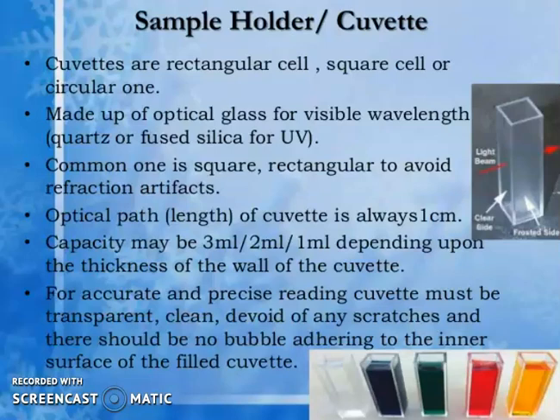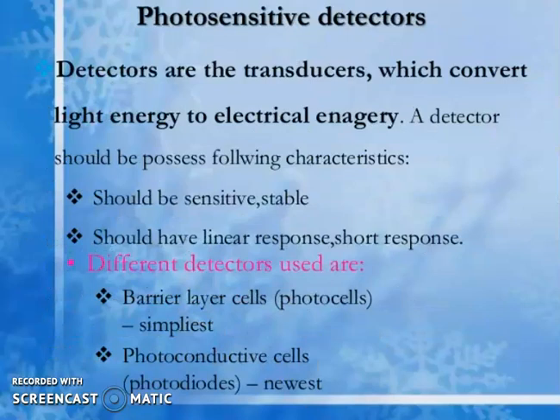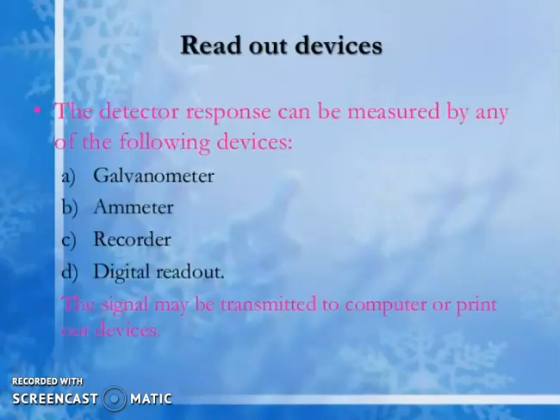Photosensitive detectors are transducers that convert light energy to electrical energy. A detector should be sensitive, stable, and have a linear response. Different detectors used include barrier layer cells, photo cells, and photoconductive cell photodiodes. The readout device measures the detector response using a galvanometer, ammeter, recorder, or digital readout; the signal may also be transmitted to a computer or printout device.